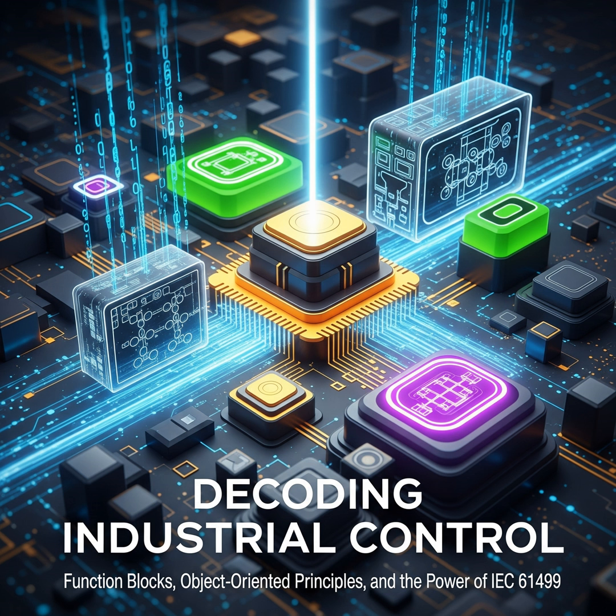And to handle this, the standard defines special types of function blocks called management function blocks. Management blocks, what do they do? They're not for the primary control logic. Instead, they provide the hooks for runtime control and management of the applications, resources, and devices. Like what kind of control? Things like programmatically creating new function block instances, initializing them, starting or stopping them, even deleting them, plus querying their status, checking connections.